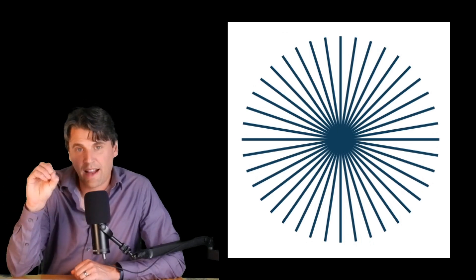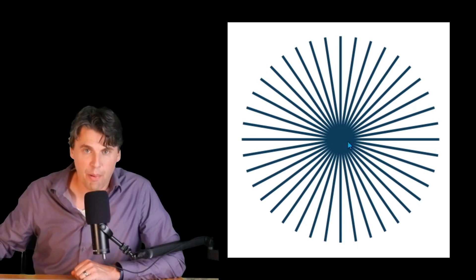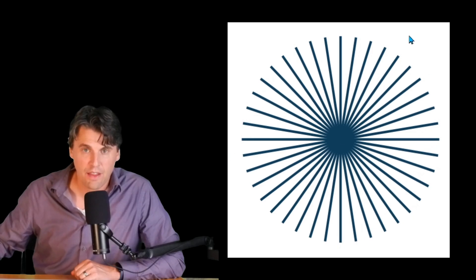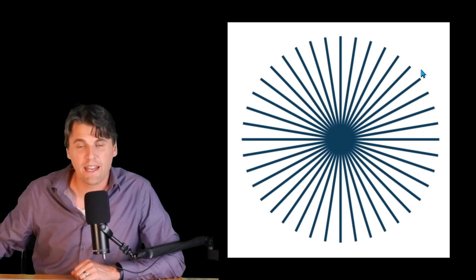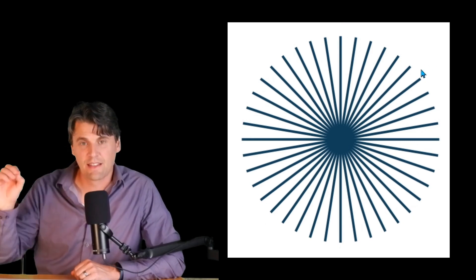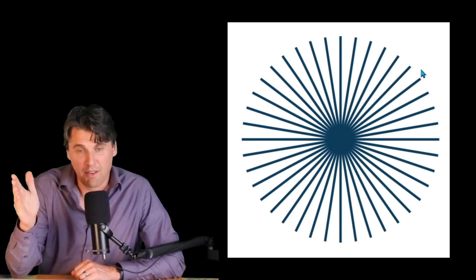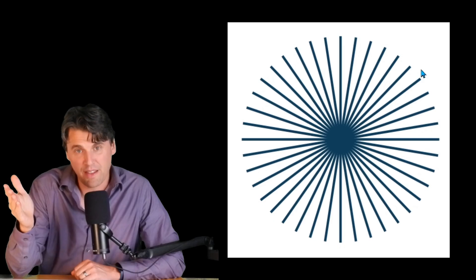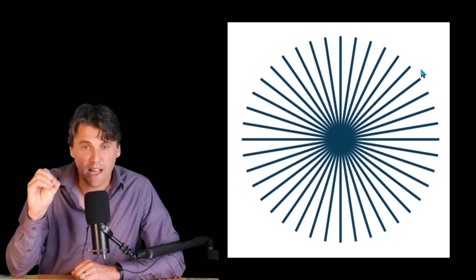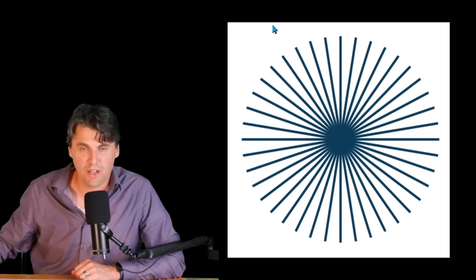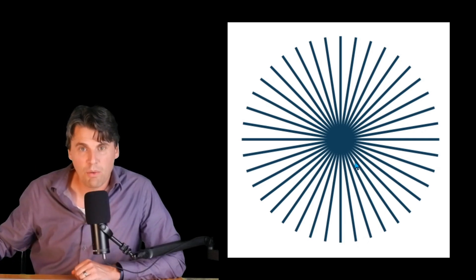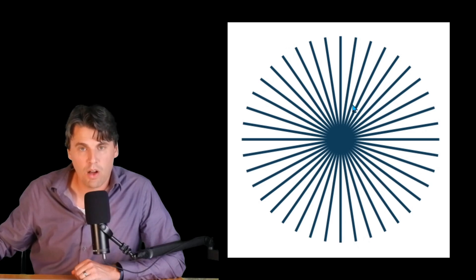One tool that's used to actually quantify this for the focal spot is actually a star pattern. If you think about these radial lines, they're all going through the center of this object here. And if you can image this, especially if you can image it on film, for instance, which has a relatively high spatial resolution, especially if you do it directly on the film itself. Again, you wouldn't image the patient in that mode because it's not dose efficient.